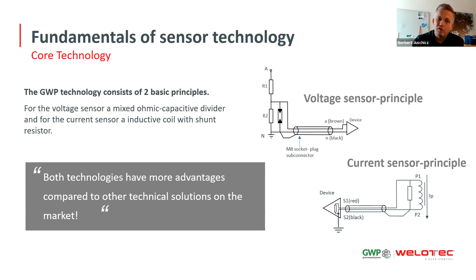So as I mentioned, you cannot buy a current or voltage sensor from the shop and put it into any kind of device. The reality is you have to customize and adjust every single sensor to the use case of the end customer. It depends on whether the use case is earth fault direction detection, load balancing, predictive maintenance, revenue measurement, or power quality. All these different use cases demand different kinds of sensors.